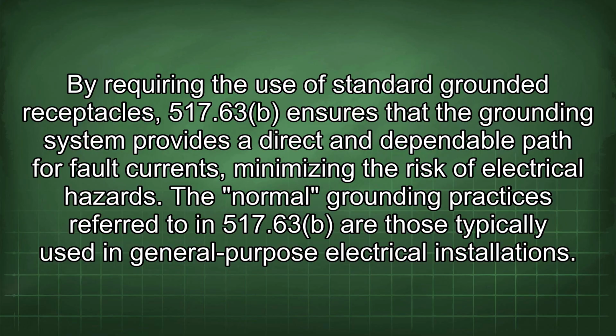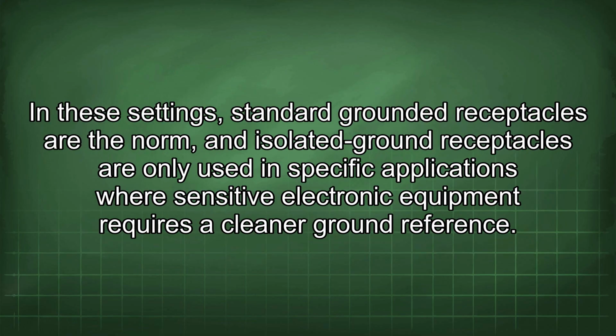hazards. The normal grounding practices referred to in 517.63 are those typically used in general-purpose electrical installations. In these settings, standard grounded receptacles are the norm, and isolated ground receptacles are only used in specific applications where sensitive electronic equipment requires a cleaner ground reference.